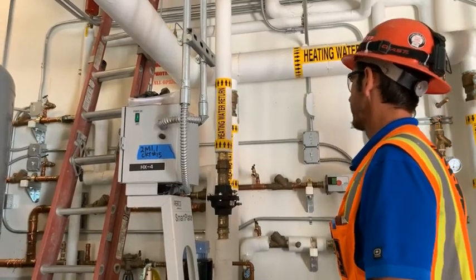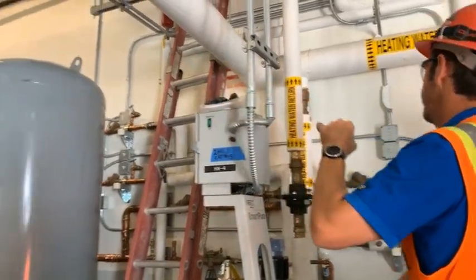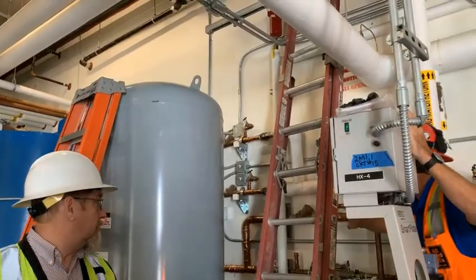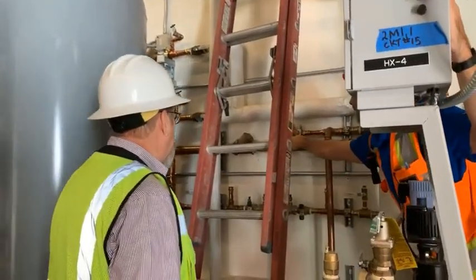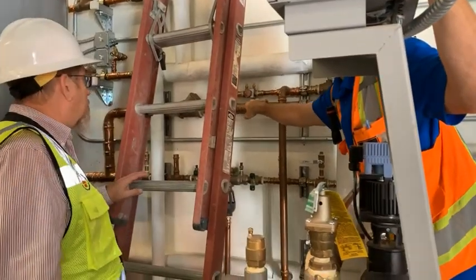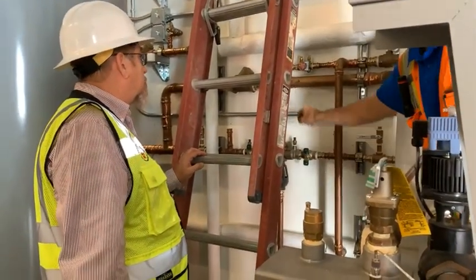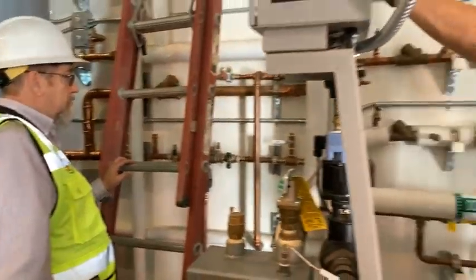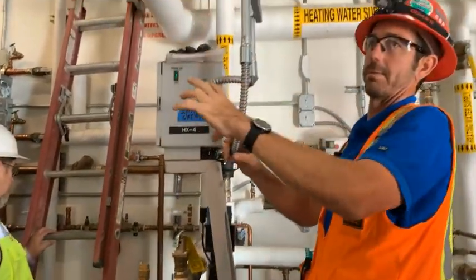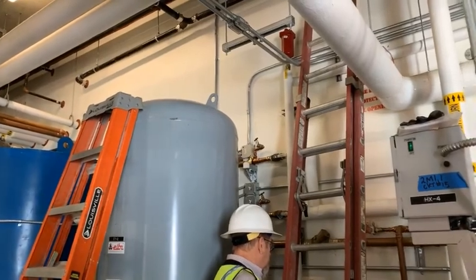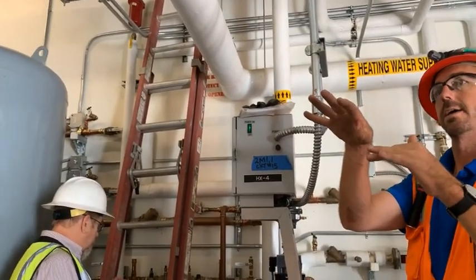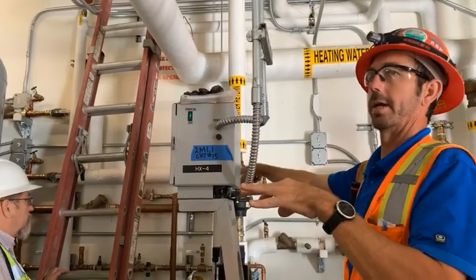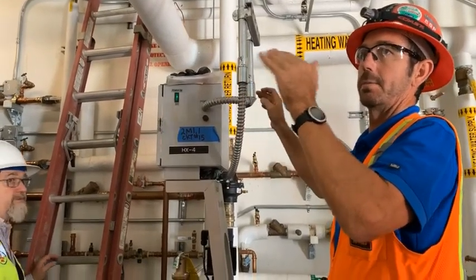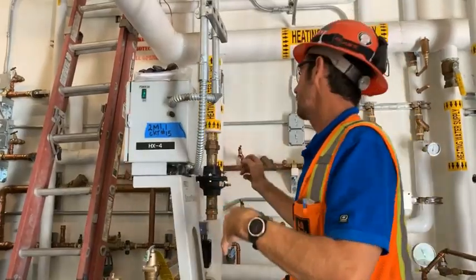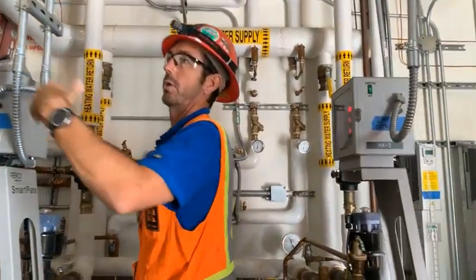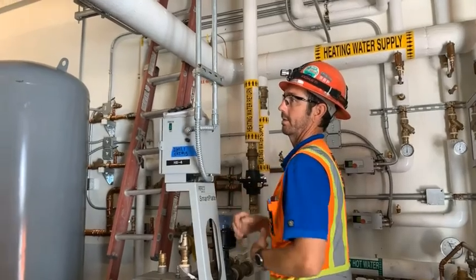So for that mixing valve that's over there, we should be around 120 now. This will be your circuit setter going into the high temperature loop. So this is the makeup water that goes through the heat exchangers on this one, and then the other circuit setter is going to be right below the mixing valve itself, and that's where the major flow is. You want less flow going through here, but just enough that it keeps you running at 120. So if it goes over 120, you would start cutting water over here, or you could open the valve over there. Does that make sense? Are you following me? But we really shouldn't need to do that now.